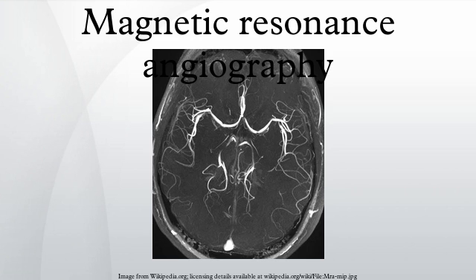Since phase contrast can only acquire flow in one direction at a time, three separate image acquisitions in all three directions must be computed to give the complete image of flow. Despite the slowness of this method, the strength of the technique is that in addition to imaging flowing blood, quantitative measurements of blood flow can be obtained.